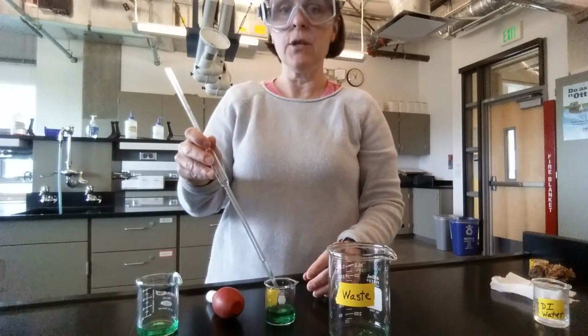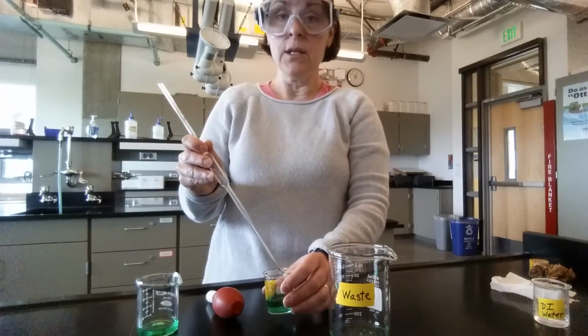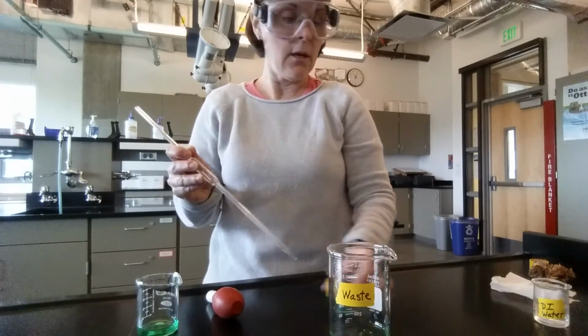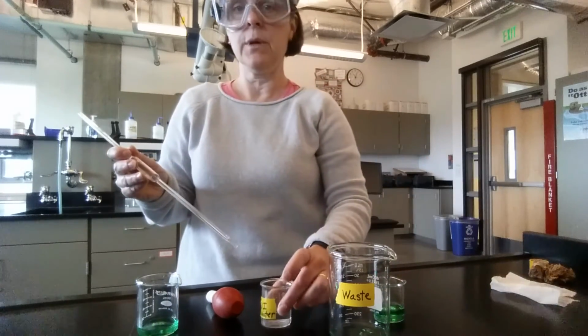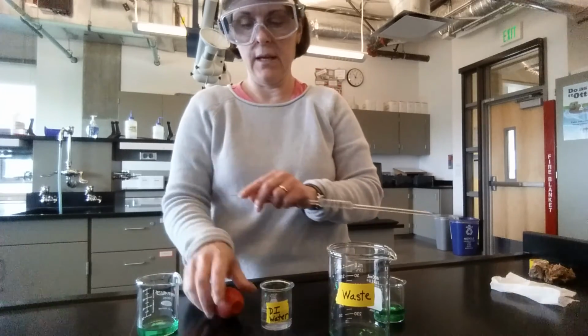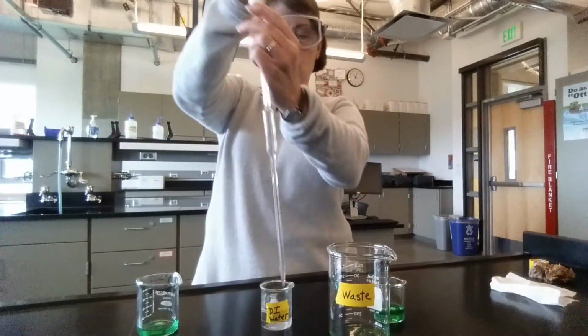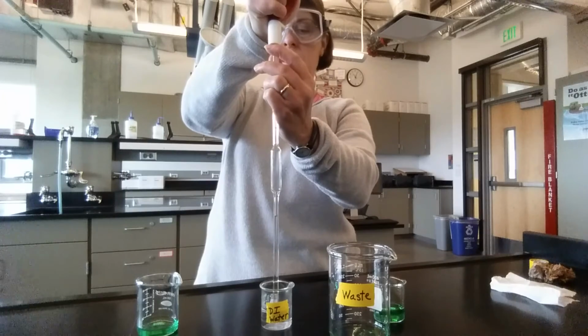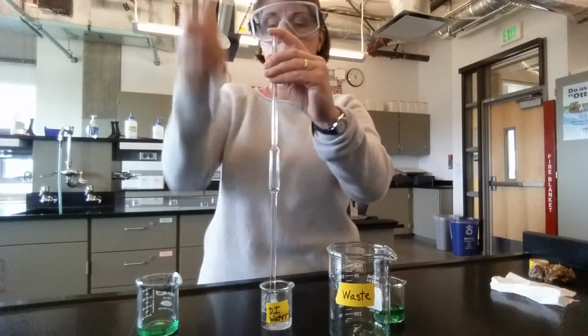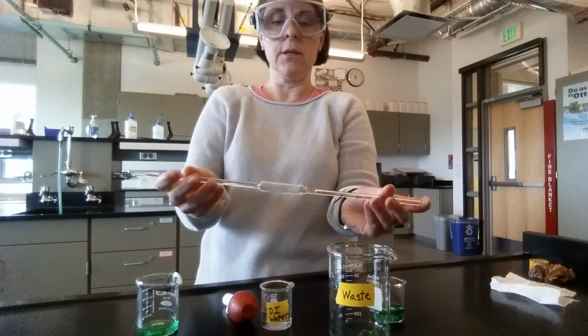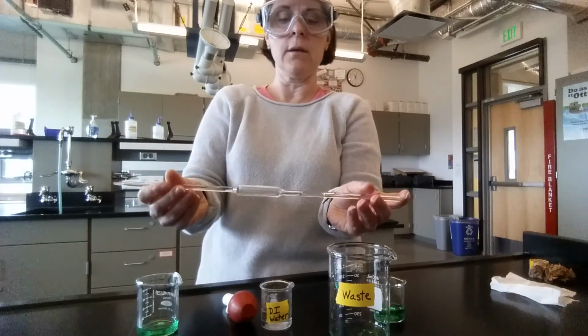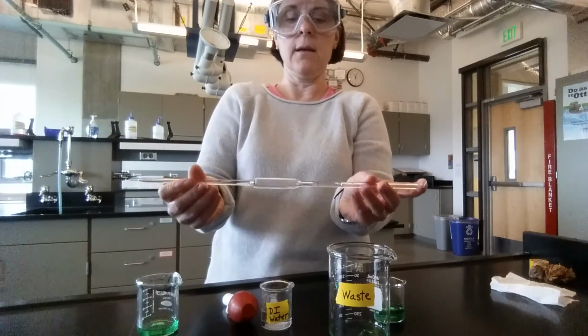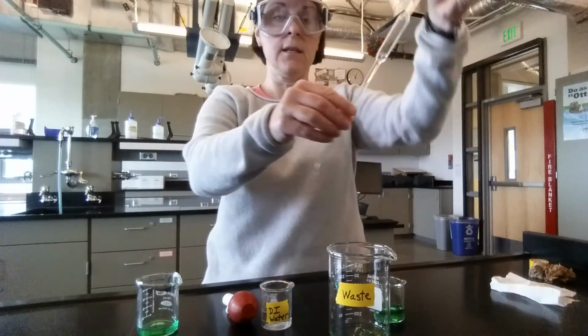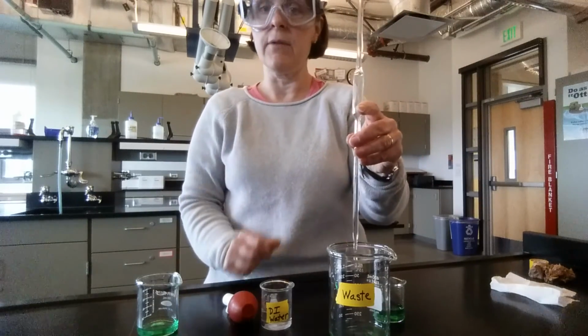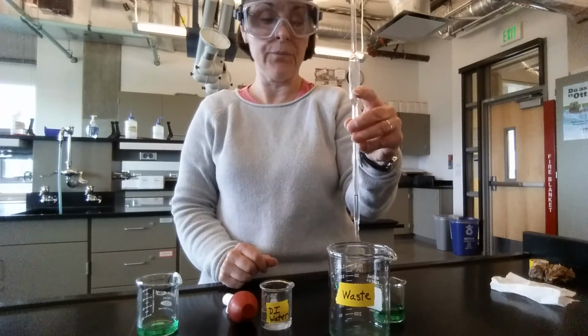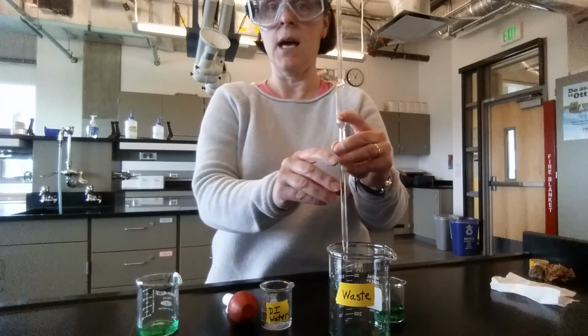When you are finished using the pipette, you need to rinse it, please. We rinse the pipette with deionized water. Again, drawing liquid, the deionized water, up into the pipette as far as the bulge. Tilt the pipette, allowing the water to access and come in contact with the inside surfaces of the pipette, and let gravity drain the water out of the pipette. Please rinse your pipette 3 times with deionized water.